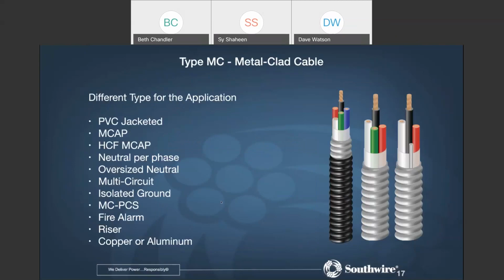So we have a lot of different kinds of these. You can get them PVC jacketed, which would make the product usable in wet locations. We have healthcare facility rated products, neutral per phase products as well. And you can see just multiples. One I'll point out, the MCPCS. This is a product that is designed with power and control conductors within the same cable. Most often used for LED lighting applications where you have a 0 to 10 volt dimming circuit, but can be used for other control applications as well. So we make these PCS type constructions for standard MC cable, for a healthcare facility MC cable. We also have variations for fire alarm applications.